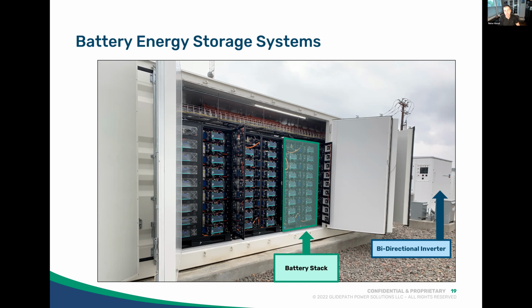We do training, no special tools are needed. The projects operate with 24/7 monitoring, and per NYISO rules they operate in fail-safe mode. If they lose communications with our control center, they disconnect from the grid automatically. Even if they're working fine, they're not allowed to operate without that oversight. Most of our facilities have at least two, if not three, separate telecom connections.